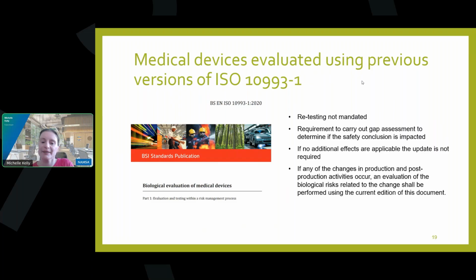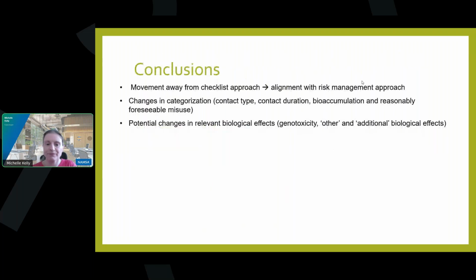If there are any changes, the last change that we've written here is no difference from the 2018 version. So if there's anything in your post-market experience, now that the device is on the market, and something's coming through that actually changes the biological evaluation, then you have to update your report. So that's nothing new. I think what's new is the gap assessment to see if additional biological effects are going to be added.